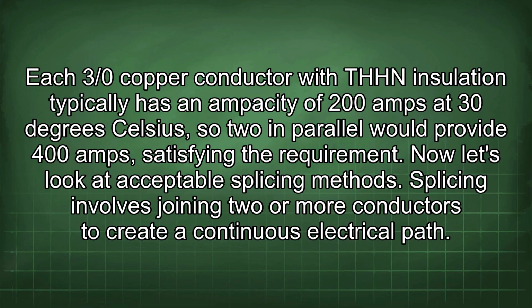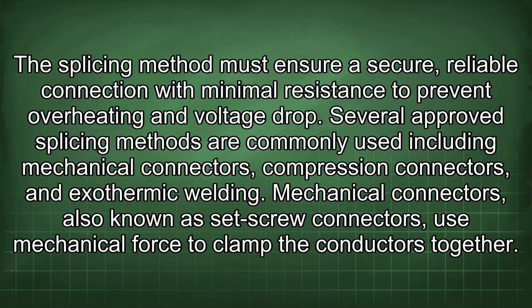Now let's look at acceptable splicing methods. Splicing involves joining two or more conductors to create a continuous electrical path. The splicing method must ensure a secure, reliable connection with minimal resistance to prevent overheating and voltage drop. Several approved splicing methods are commonly used, including mechanical connectors, compression connectors, and exothermic welding.